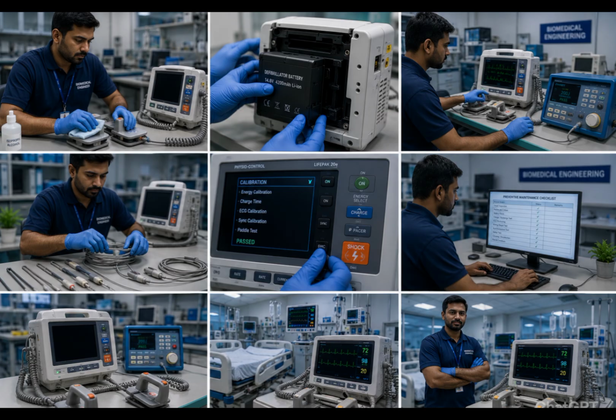Next is the final testing. In final testing, you have to check the power on sequence, whether the battery is charging, and ECG monitoring. You have to check the paddle connection, shock delivery system and all. After checking, you can confirm that the defibrillator is now functioning correctly and is ready for emergency use. So, proper troubleshooting and preventive maintenance help ensure patient safety and reliable equipment performance.